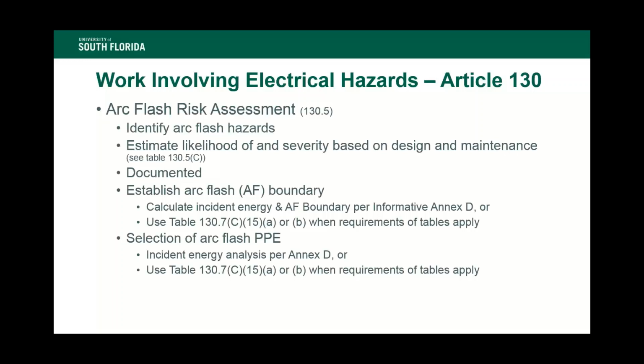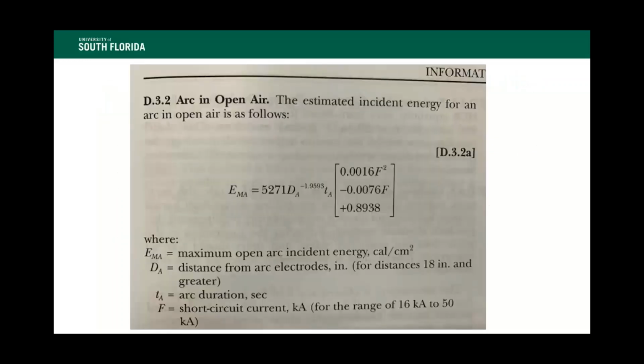The arc flash risk assessment will also allow us the opportunity to select the appropriate level of arc flash PPE based on either the incident energy analysis per our use of Annex D, or again, the use of Table 130.7(C)(15)(A) or (B). Here's a sample of the incident energy calculation in Informative Annex D.